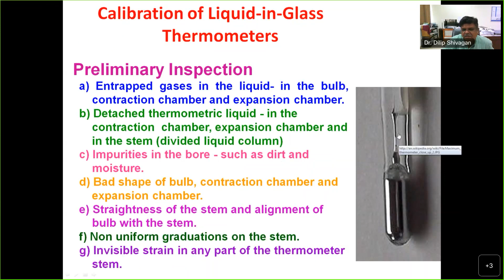For stem correction, we note the thermal conductivity and the amount of thermometer dipped into the bath and out of the bath. With the temperature difference out of the bath and within the bath, you can take this as a stem correction. For a very fine thermometer, this matters a lot. So an additional component will be stem correction. But if you use it as per the fabrication or as per the advice, then you need not take the stem correction into account. Another important industrial thermometer is the thermocouple thermometer.